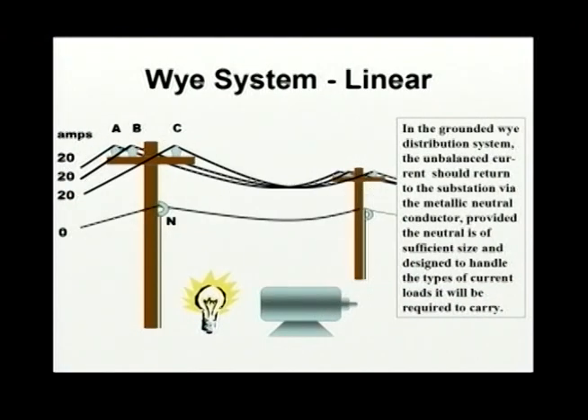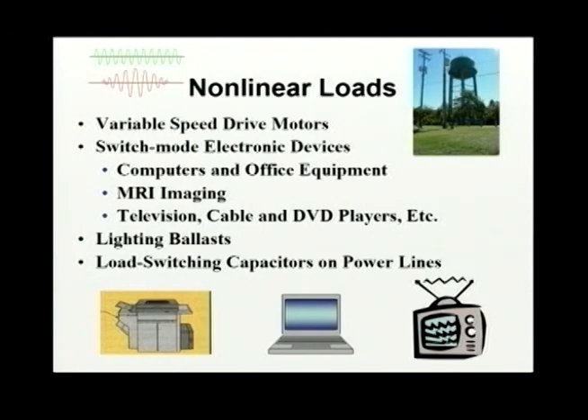In the grounded Y distribution system used throughout North America, the unbalanced current should return to the substation via the metallic neutral conductor, the lowest line in the photo, provided the neutral is of sufficient size and designed to handle the types of current loads it will be required to carry. Since the early 1970s, we have seen a dramatic increase in the use of modern electronics, which are nonlinear loads. Nonlinear loads change alternating current to direct current.